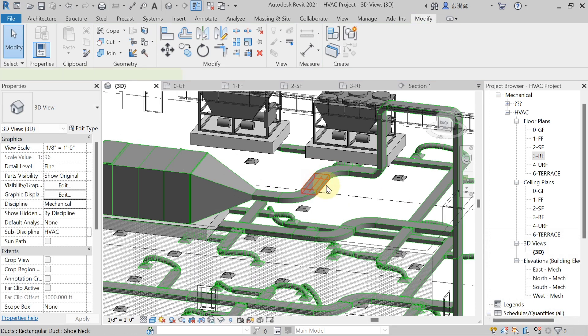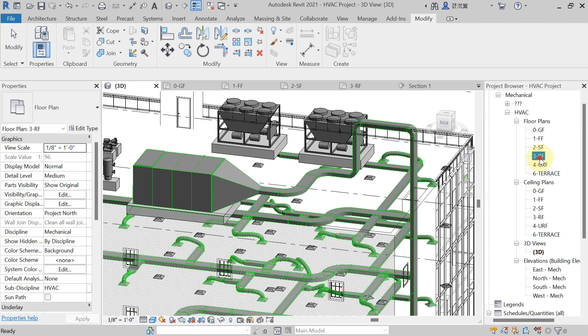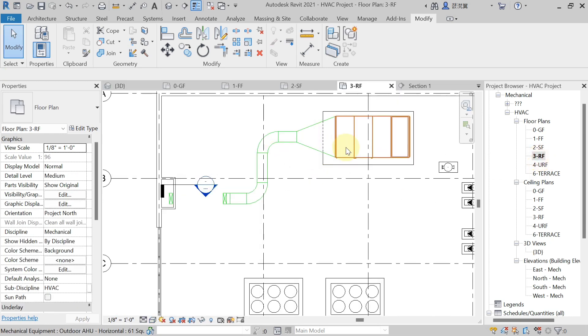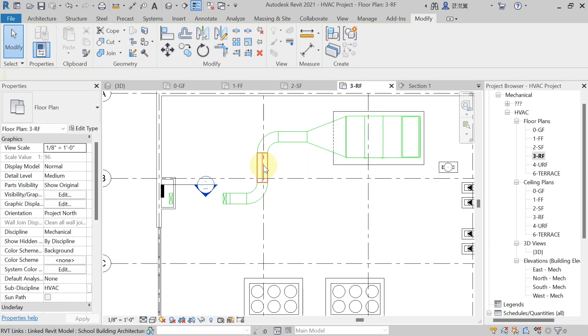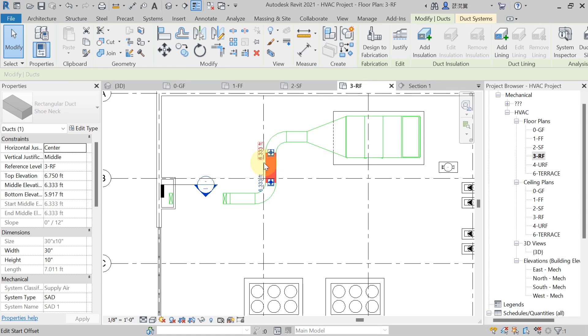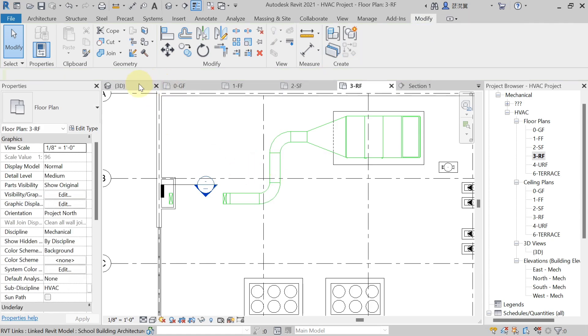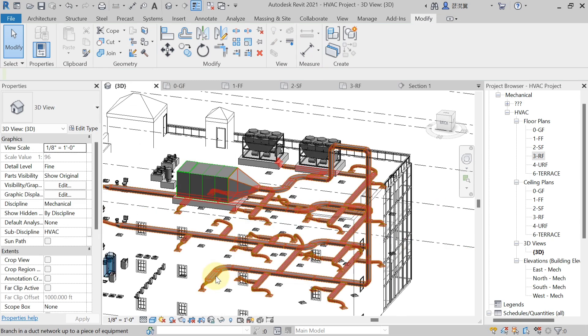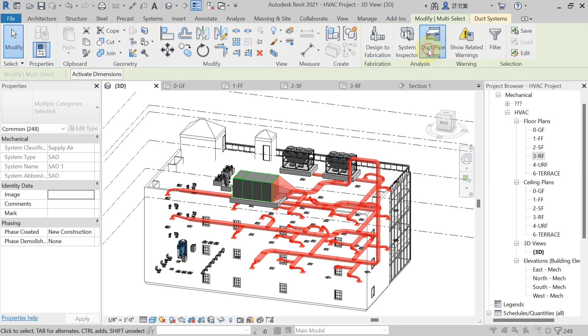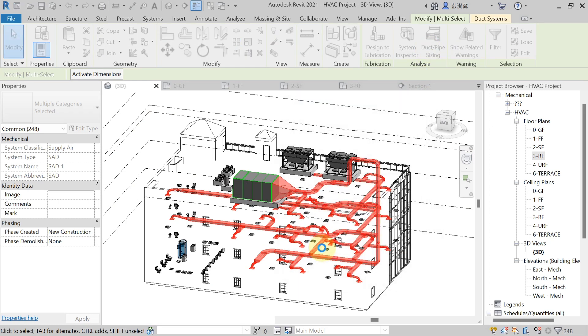To fix the fitting issue, move the duct a little bit on the roof floor — move the AHU and plinth as well. Once resolved, again select the complete ducting layout, hit Duct or Pipe Sizing, select Equal Friction method, and click OK. Now the sizing completes successfully up to 100 percent because we have resolved the connectivity problem.